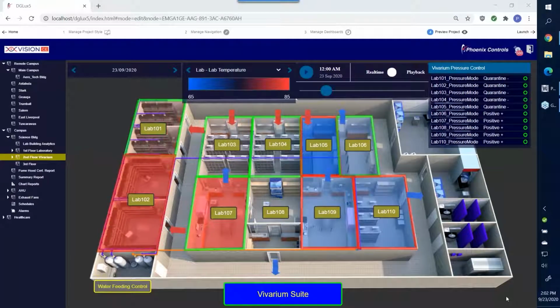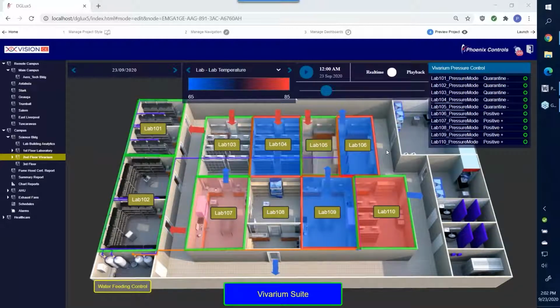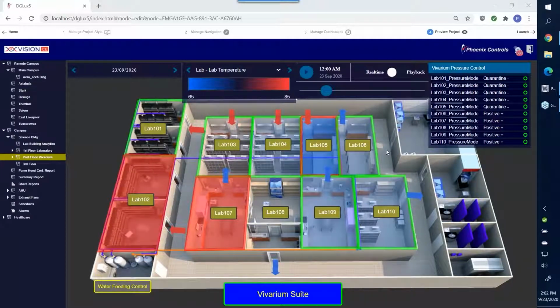In addition to the gradients discussed, especially for a vivarium, there are many applications for giving local ability to control pressurization modes, such as when there's infection or immune-compromised animals. You need to make it a quarantine space, a positive space, or in some cases a sealed space. In conjunction with the Phoenix Air Valve, you have a guaranteed plus or minus 5% accuracy over the life cycle of the valve.